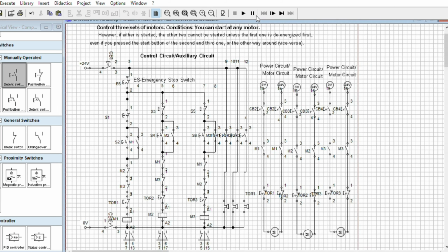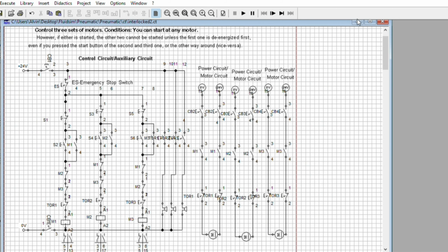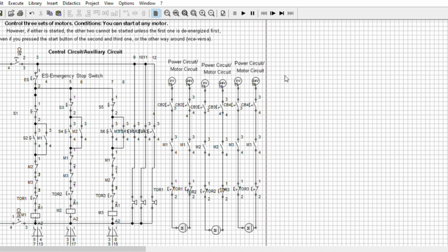Okay, this is about the double interlock circuit. So again, if we are going to interlock a circuit, use the normally closed contact. Normally closed contact. Interlock this one, normally closed contact. Normally closed contact. Normally closed contact.